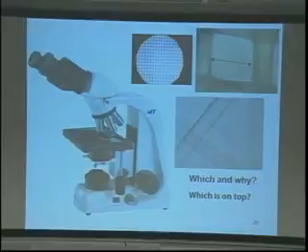So it's magnified in our case by two sets of lenses, the objectives and the oculars. These are fixed magnification, 10x. We're not going to change those. So the oculars are fixed at 10x. But we can change the objectives we use by rotating this turret. So we can have the 4x objective in place, we can have the 10 or the 20 or the 40. So you can change the total magnification by changing the objectives.